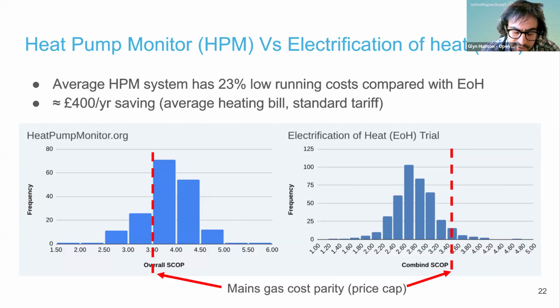And those red lines there just show the cost parity with mains gas. As you can see, not many systems from the electrification of heat were lower cost than gas. That is on a price cap tariff. If on a smart tariff, especially with heat pumps and solar, it is possible for a heat pump to achieve cost savings over mains gas with a lower performance. But obviously, the higher the performance, the easier that is, and the less susceptible the user will be to fluctuations in energy prices. Next slide, please, Will.